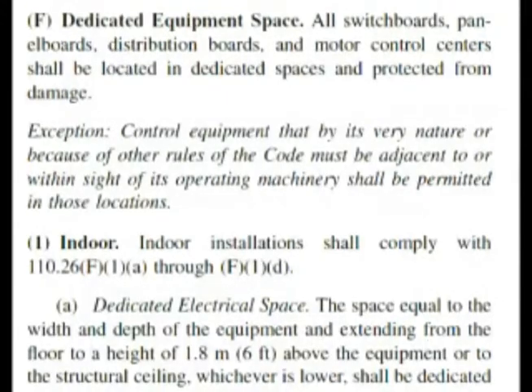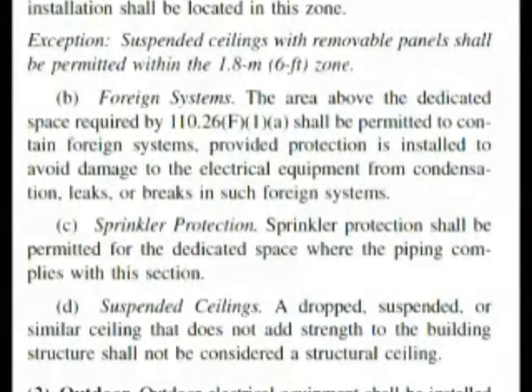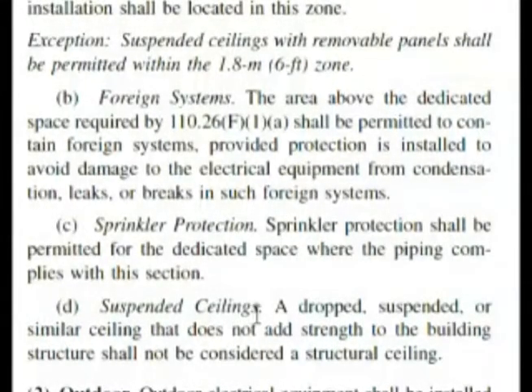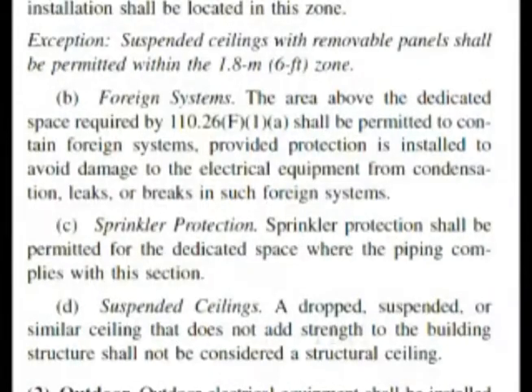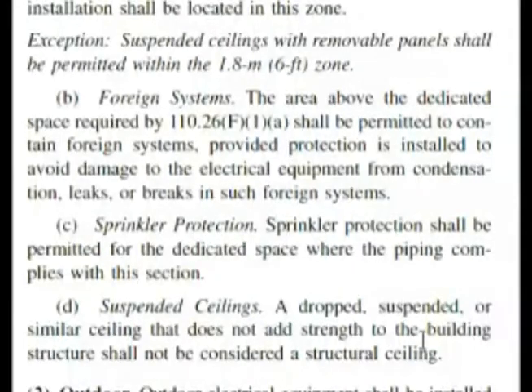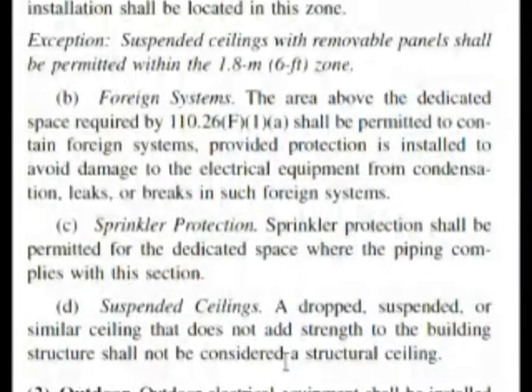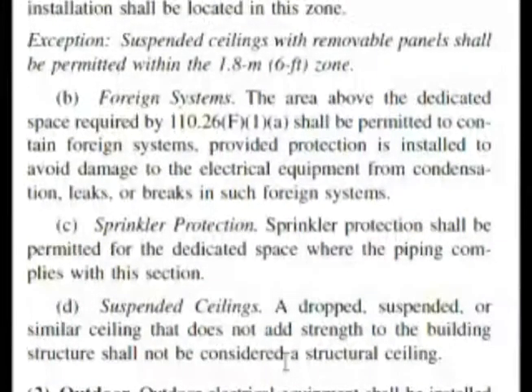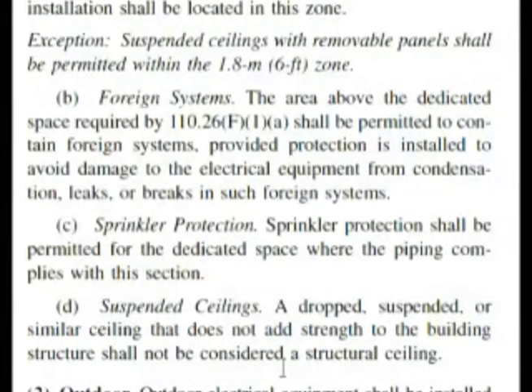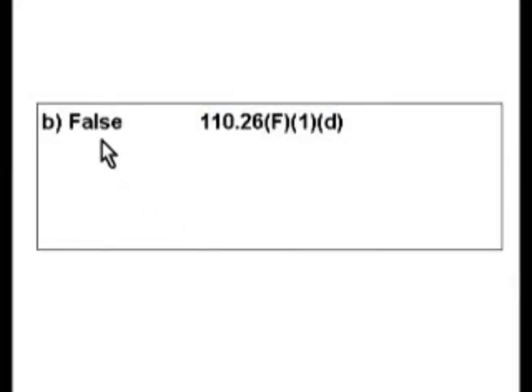We find here dedicated equipment space, and our question starts off with the dedicated space above a panel board, so this looks like a good place. Now we start going through these smaller italic headings. We find subsection D, suspended ceilings: a dropped, suspended, or similar ceiling that does not add strength to the building structure shall not be considered a structural ceiling. The statement in the question said it was considered a structural ceiling, but the code says it shall not be considered a structural ceiling. This makes the answer to question 74 false, which is choice B.